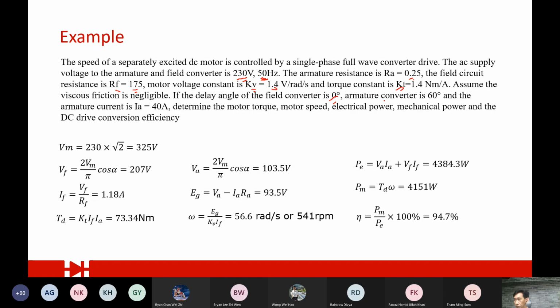The armature converter firing angle is 60 degrees, and the armature current will be around 40 amps. We need to determine the motor torque, the motor speed, the electrical power, mechanical power, and lastly the DC drive conversion efficiency.